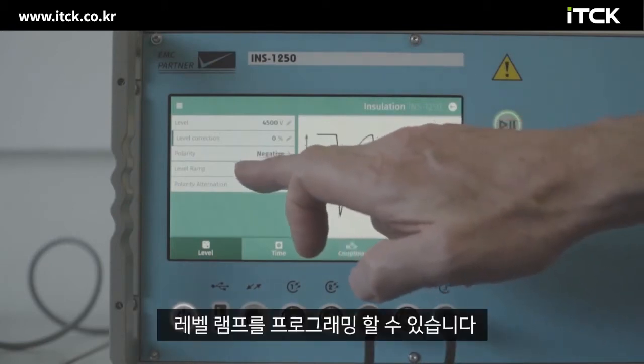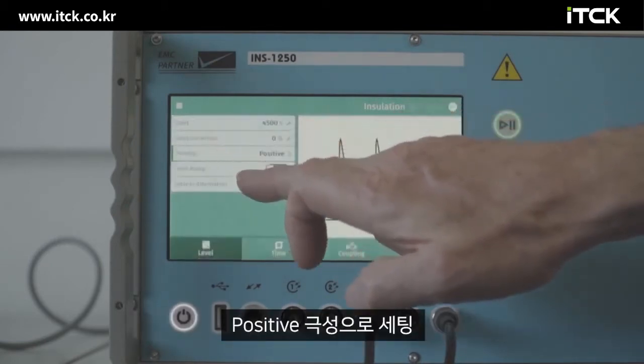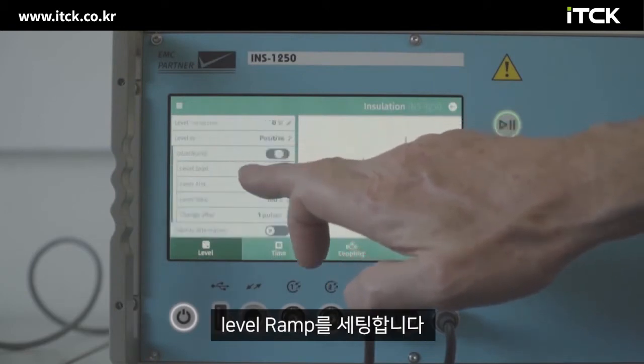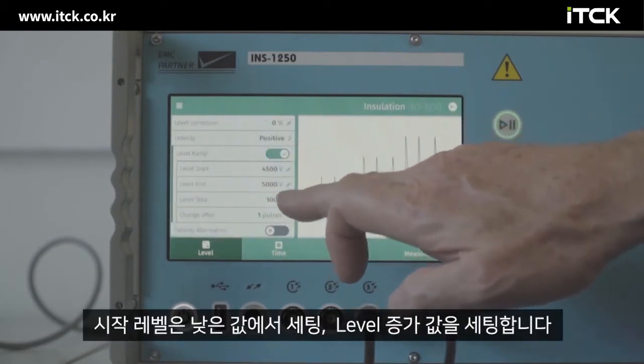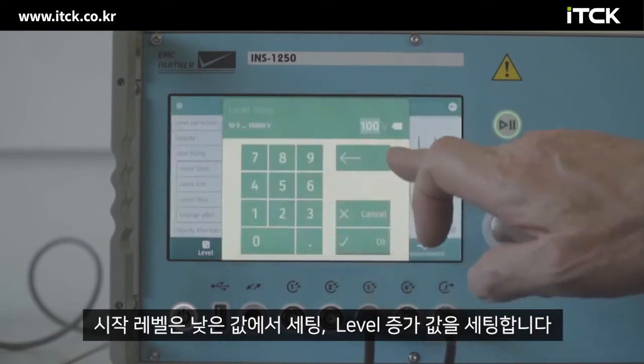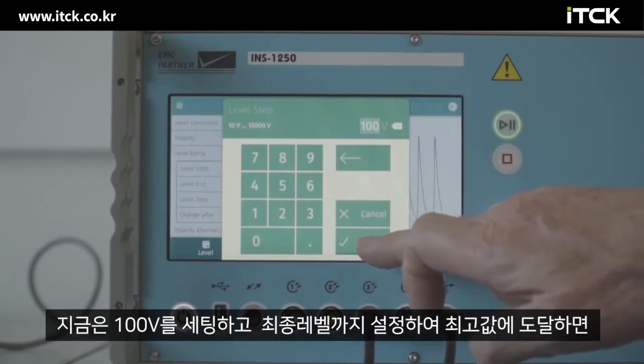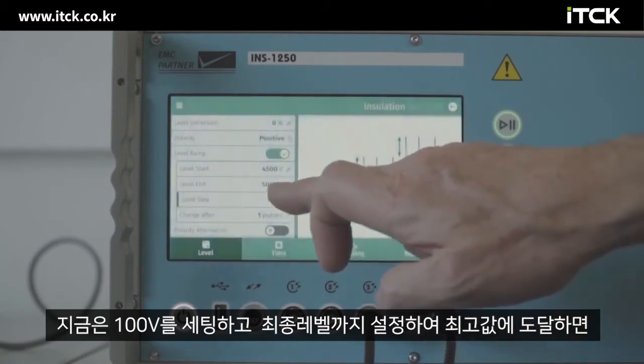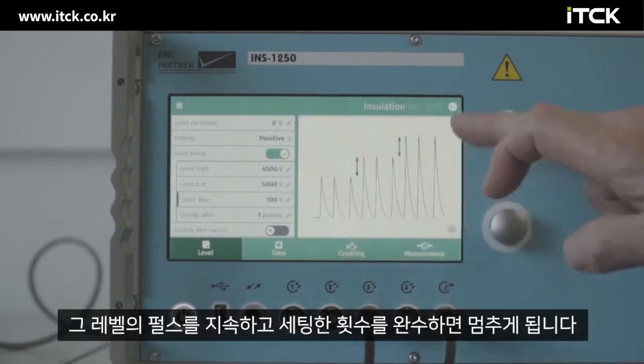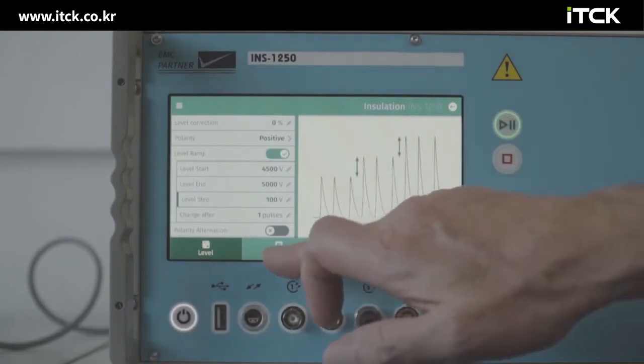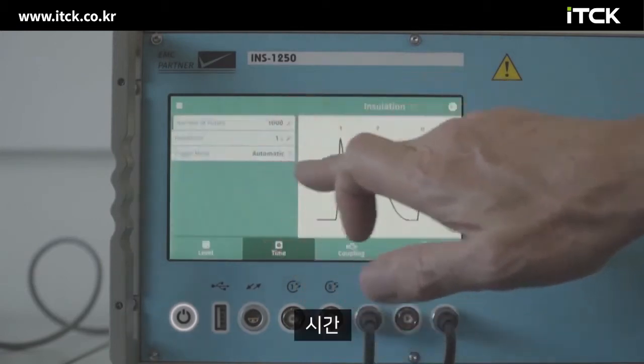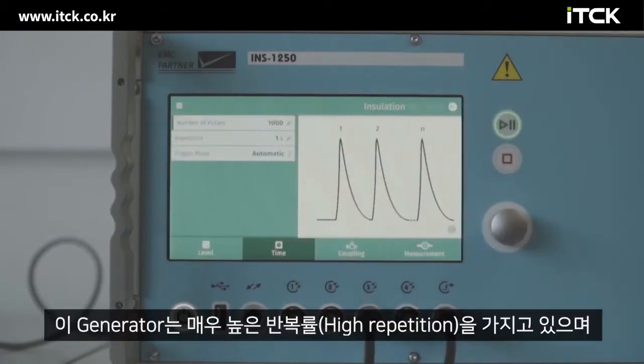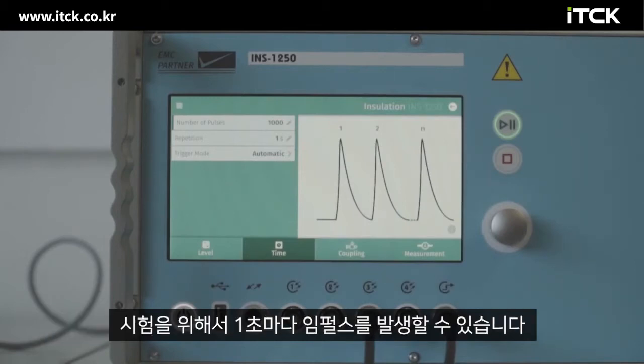We can program a level ramp, take it back positive polarity, a level ramp, so that we can start at a low level, increase the voltage in different steps, in this case 100 volts, up to a final level where it will then stop and continue to pulse at that level. Time. This generator has a very high repetition. We can produce impulses every second for the test.